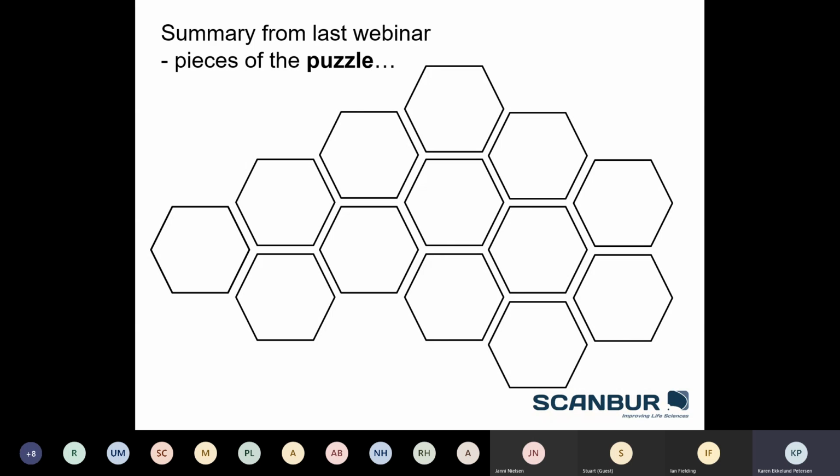This webinar was an introduction to the concept of humidification on cage level, and also how we can make accurate control of relative humidity in the cage possible. What we discussed at the last webinar is an air handling unit called the ScanClime, that can humidify air in IVC cages and also in cabinets like Scantainers. It works like a normal air handling unit, but it can also humidify the air, and some units can also dehumidify the air. And it can be done quite accurately with a relative humidity accuracy of ±3%.